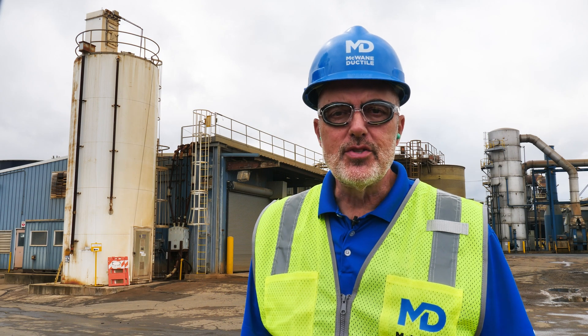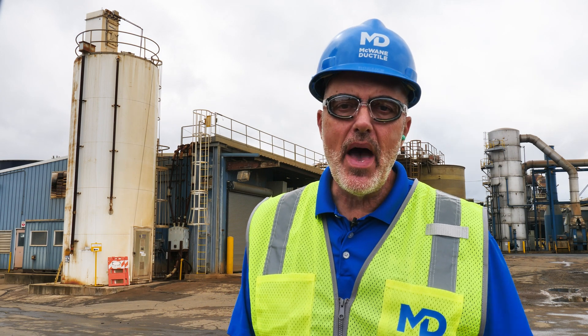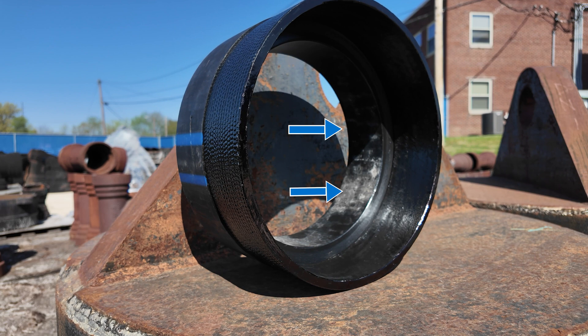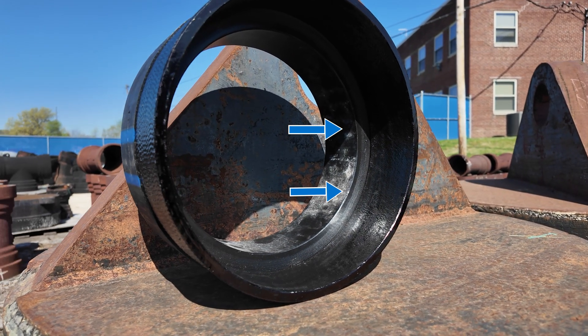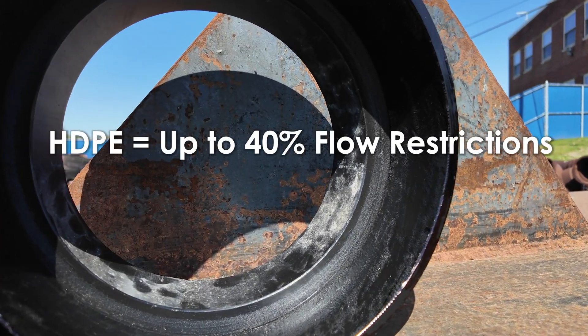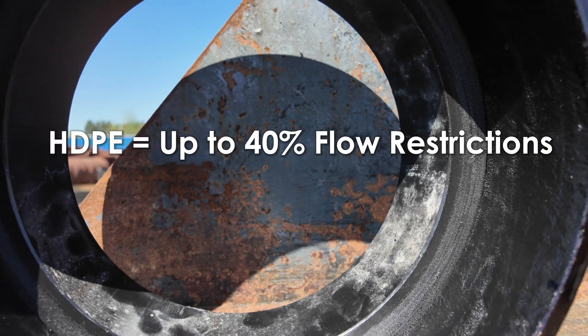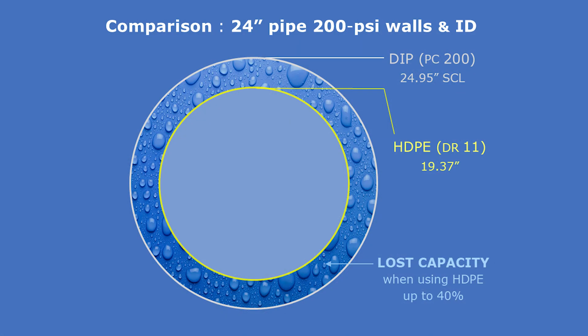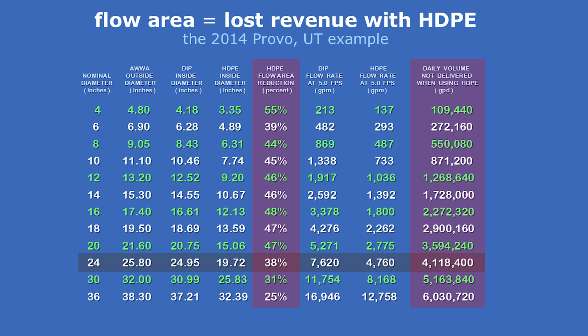Another area to consider is the operating cost of a given pipeline. Size does matter when comparing products, best represented by demonstrating the inside diameter of ductile iron pipe versus HDPE. Ductile iron pipe has a larger inside diameter than HDPE, allowing for a less restrictive flow as opposed to the smaller inside diameter of polyethylene, which causes flow restriction of up to 40 percent and adds pumping costs to convey water through the system. Typical flow comparisons dictate that polyethylene must be upsized when compared to ductile iron pipe to achieve the flow rate required by the project design.